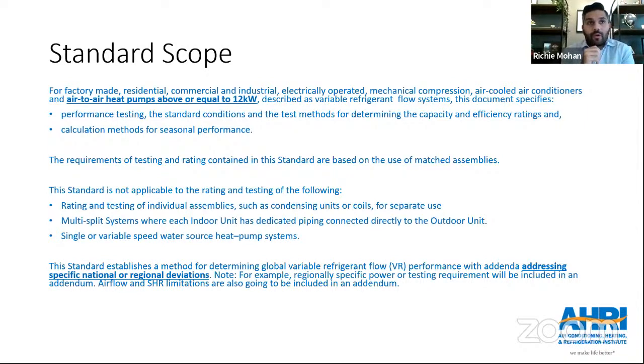We've also discussed what percentage of the indoor units should be operating in cooling versus heating at the same time, and whether that's representative of the field. Today in the AHRI 1230 standard, we caught this really late: we basically put 50% of the indoor units in cooling and 50% in heating, and run a test. But that's not really representative of the field, because technically you might have 25% of indoor units in cooling, 25% in heating, and the rest just shut off.